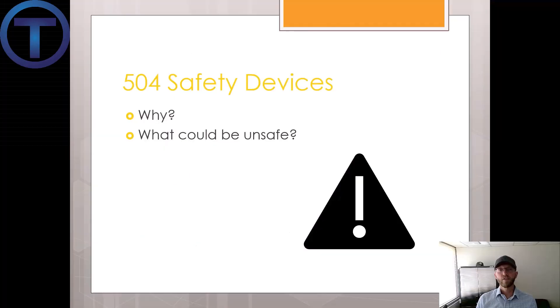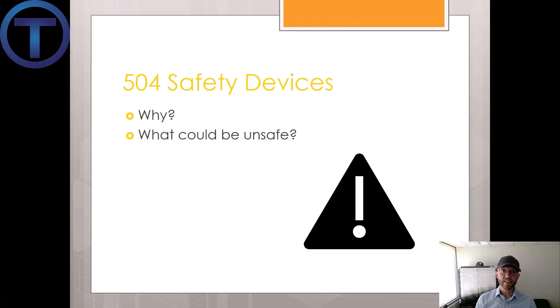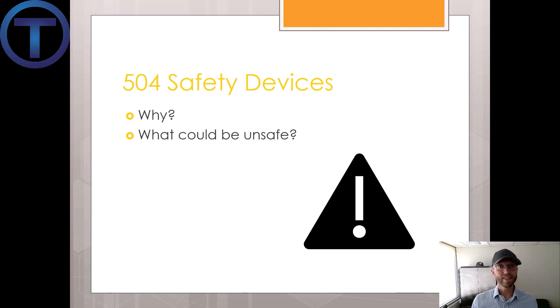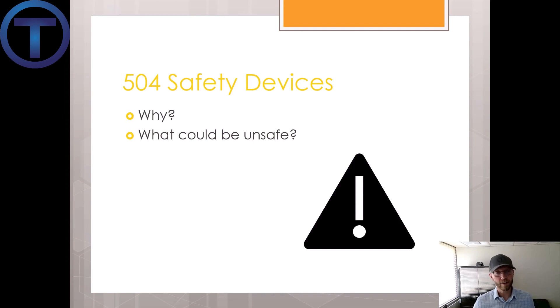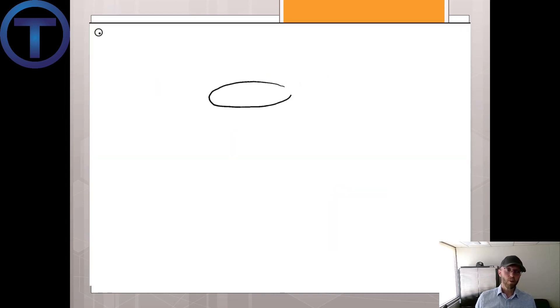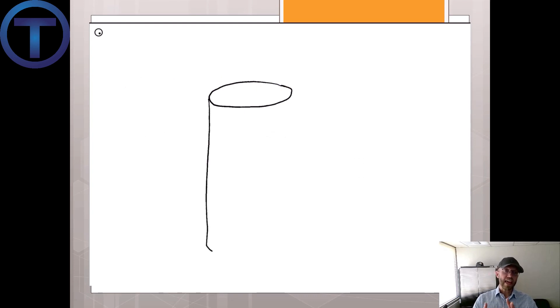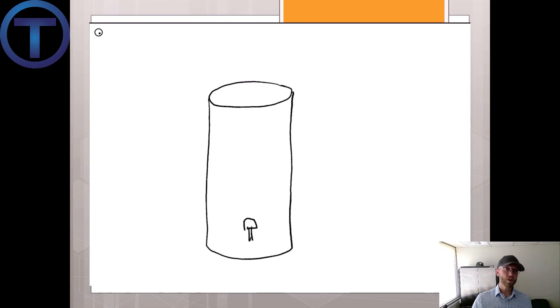In section 504, we get information about safety devices. There are a number of things that could go wrong with a water heater. 504.1 gives us information on anti-siphon devices. Let me give an example of the dip tube: a dip tube is the cold water pipe that pushes water in a tank-type water heater to the bottom where it will be heated at the burner.